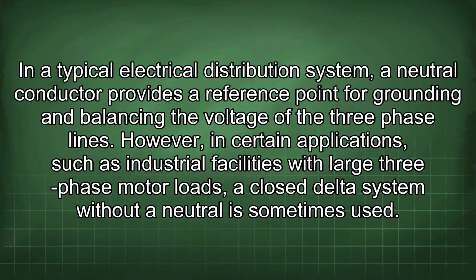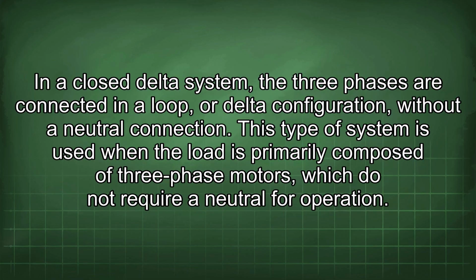In a typical electrical distribution system, a neutral conductor provides a reference point for grounding and balancing the voltage of the three-phase lines. However, in certain applications, such as industrial facilities with large three-phase motor loads, a closed delta system without a neutral is sometimes used. In a closed delta system, the three phases are connected in a loop, or delta configuration, without a neutral connection.